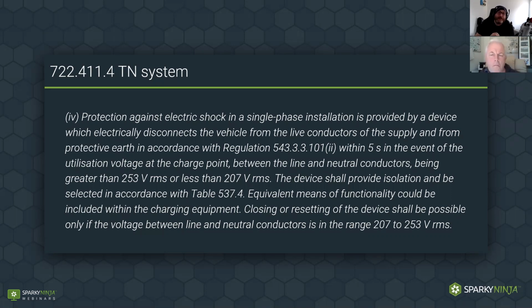Equivalent means of functionality could be included within the charging equipment. Closing or resetting of the device will be possible only if the voltage between the line and neutral is in the range. So it'll only operate if the present voltage between line and neutral is within the legal limits that BS 7671 has.